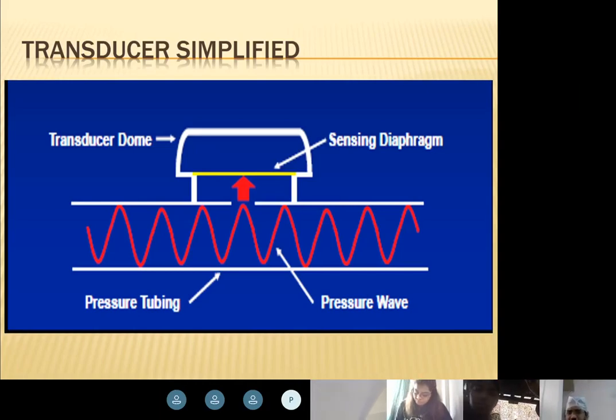Say your arterial waveform is coming from your artery on the left side. There is a pressure happening. That pressure goes up and down, systolic, diastolic, systolic, diastolic, systolic, diastolic. That's the pressure. If you see in movies when the radial artery is cut, the blood comes out in spurts. That pressure is what is getting converted onto the water column. It is not the blood coming out. It is the water column that is there. The pressure is applied on that water column, and then that pressure comes up and down, reaches the sensing diaphragm. Then the diaphragm goes up and down. The kinetics of the diaphragm change, and the change of the kinetics of that diaphragm now relays into an electrical signal, and that electrical signal is what you're seeing on the waveform as a graph or as a number.